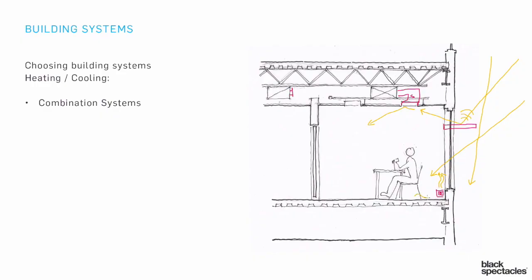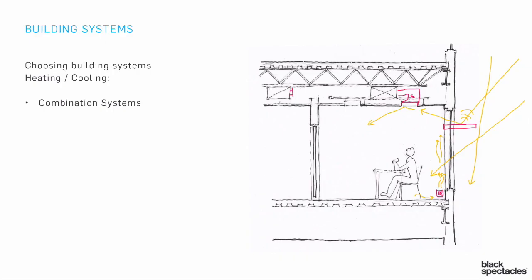Why do we have hot air rising when that's a radiator? Because cold air from the floor comes down underneath and gets close to that hot water pipe. It warms up and creates a convective current in front of the window. One thing that convective current does is create a barrier between the person and the window. The person and the window — that cold body — want to trade energy through radiation. In winter, the person is the warm body giving off heat to the cold window. That convective current helps dampen that connection.